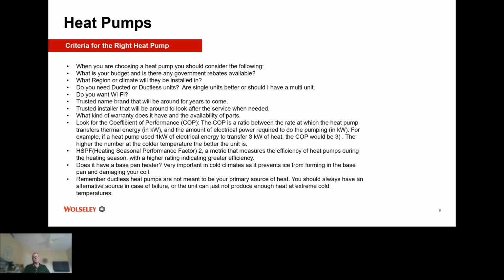Very important too, look for the coefficient of performance. It's called COP, the ratio between the rate at which the heat pump transfers thermal energy in kilowatts and the amount of electrical power required to do the pumping in kilowatts. For example, if a heat pump uses 1 kilowatt of electrical energy to transfer 3 kilowatts of heat, the COP would be 3. The higher the number at the colder temperature, the better the unit is. And of course, the better the unit is, the more you're going to pay for it as well. But you'll get your money back in the long run, just in electrical savings.